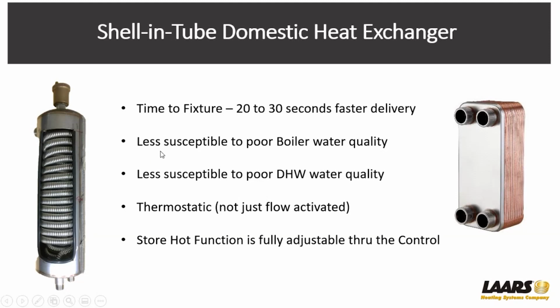Also, shell and tube design is less susceptible to poor boiler or hydronic water quality. It's also less susceptible to poor domestic water quality. Why? Because these plates are real small and you can plug these up. With this heat exchanger design, these are 3/4-inch corrugated tubes, so less likely to plug up. We're also thermostatically adjusted, so we have a built-in mixing valve right inside our boiler, and it's digitally activated, so you set it up digitally with the display. It's not like a shower valve that you have to get in with an Allen wrench and adjust that mix. You basically set it at 120, 125, 118, whatever you need, that will adjust internally.